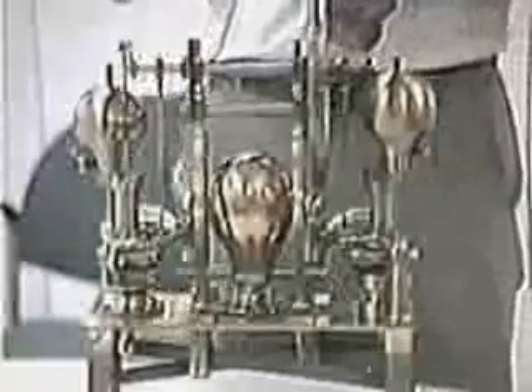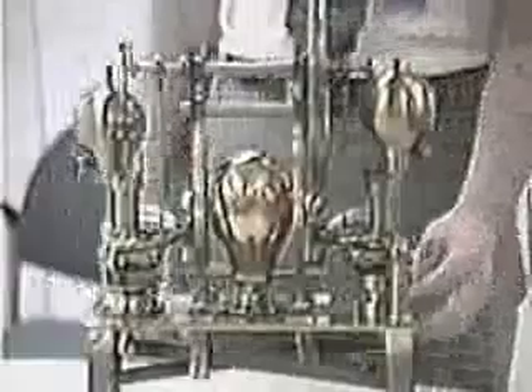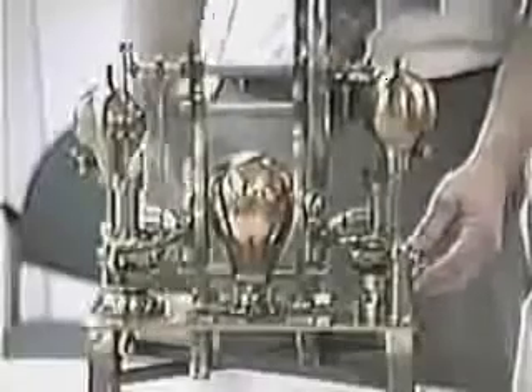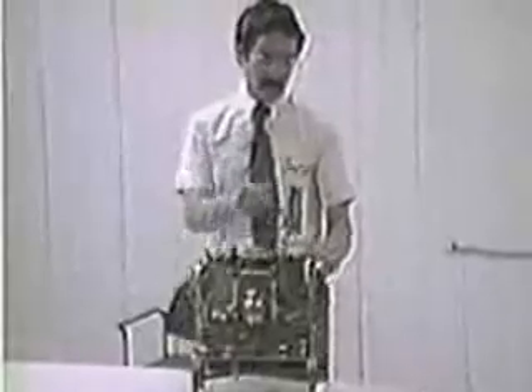So when you close the valve on high velocity water, what do you get? You get a water hammer. You get that pounding. Water hammer is when you close the faucet in your sink and the pipes bang in your basement. That's water hammer. There's infinite pressure in that. So that pressure, I did a computer model of what happens in here. And of course, a computer model is based on ideal conditions, which this isn't. But I was surprised that it showed within 8 cycles of this valve opening and closing, the pressure goes to infinity. Now that's an ideal situation, which this isn't. So we got the high-speed stream of water coming through the valve system, pushing this piston up, and would cause a little bit of rotation.